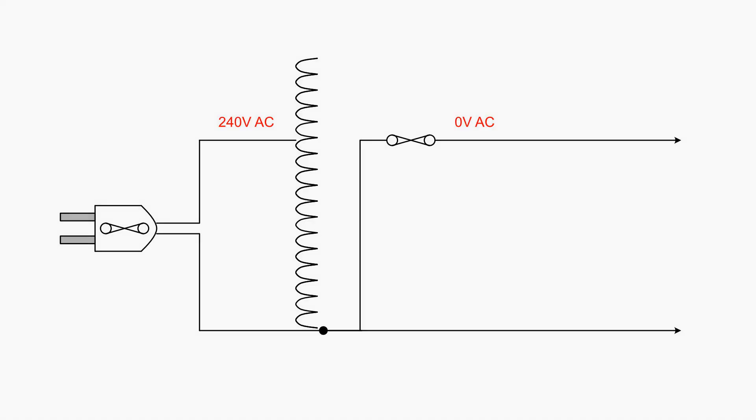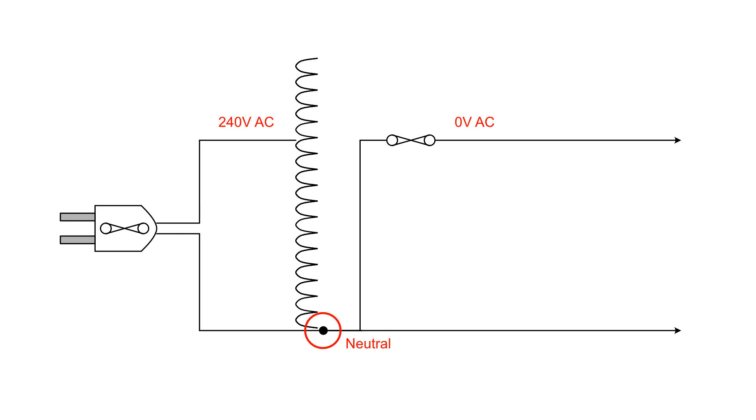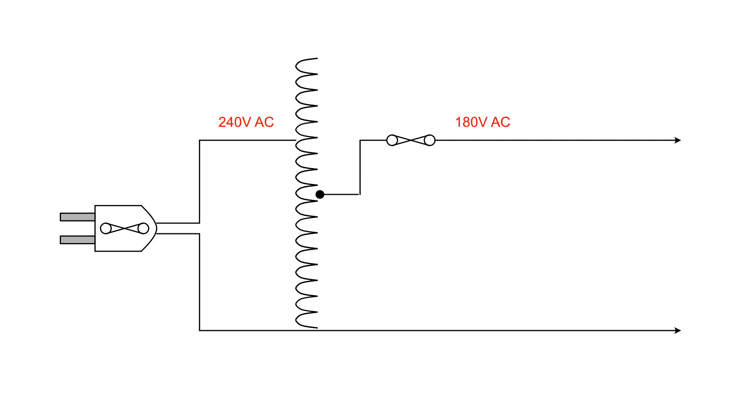So what is a variac? This is also called an auto transformer—it's a means to provide a variable AC supply. It consists of a single winding on what is generally an iron core. The winding is usually tapped about seven-eighths of the length. The AC input is connected between this tap and the end of the coil. The neutral wire is also connected to the end of the coil. A wiper connected to a rotary knob is then able to tap into the coil windings to provide a voltage for the output.